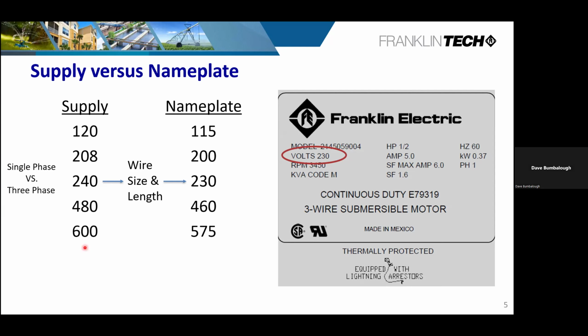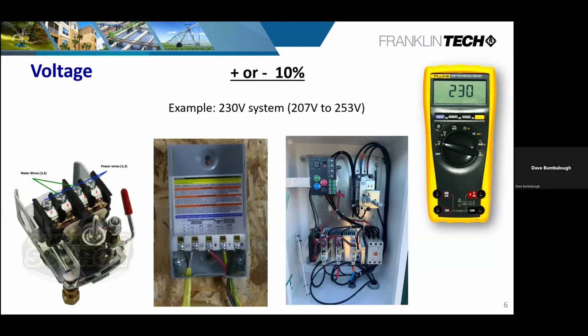But it's very crucial that these voltages stay in check. Therefore, the manufacturers can still continue to build their products without having issues. So with that said, there are several places that you can check that voltage. Sure, you can go right to the breaker panel itself, check the voltage there and make sure it is where it needs to be. The voltage supply coming in, in most cases, is plus or minus 5%. Now, we give a little bigger tolerance than that on our equipment. Well, we're allowed plus or minus 10%.